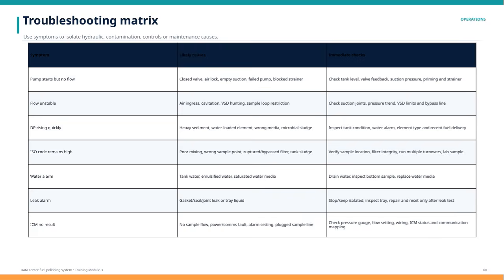A quick rise in differential pressure, or DP, often indicates heavy sediment buildup, water in the filter element, use of the wrong media, or microbial sludge. Here you should inspect the tank's condition, check any water alarms, look at the element type, and review recent fuel deliveries. When the ISO cleanliness code remains high, it often points to poor mixing, incorrect sample points, damaged or bypassed filters, or sludge in the tank. The recommended actions are to confirm the sample location, test filter integrity, perform multiple turnover runs, and send samples to the lab for analysis. For water alarms, potential causes include tank water accumulation, emulsified water, or saturated water media. Draining the water, inspecting the bottom sample, and replacing the water media are the key remedies.